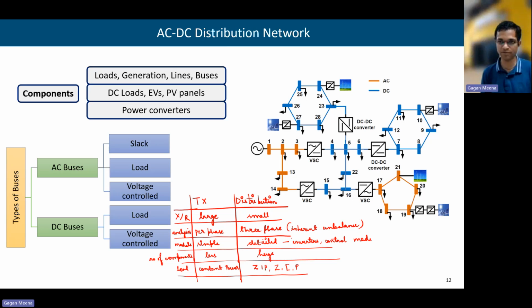That's why it becomes more involved, and the algorithms which we use for the transmission system are no longer applicable for the distribution system, because of this small X by R ratio in the distribution system, which results in convergence issues for the conventional Newton-Raphson and Gauss-Seidel power flow methods. That's why we have modified Newton's method, forward-backward sweep, and other types of methods specifically designed for the distribution system.